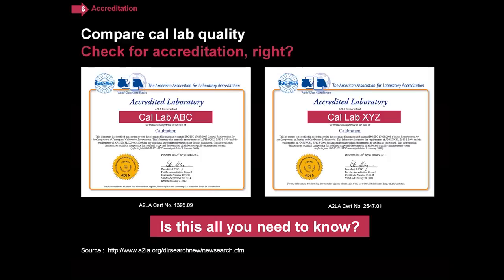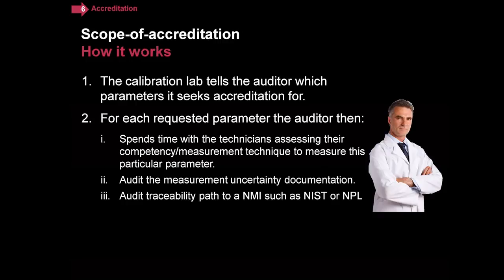The way accreditation works is that during the audit, right up front, the lab tells the auditor the parameters they want to be audited against. For each one, the auditor spends time with the technicians to make sure they know to do all the appropriate things — for example, whether they use torque wrenches for RF microwave, or how careful they are about temperature for gauge blocks. They also audit the measurement uncertainty documentation for the lab's calibration measurement capability. CMC — calibration measurement capability — is the list of the best measurements and associated uncertainty that lab can make. Finally, they audit the traceability paths that we looked at in Module 3.